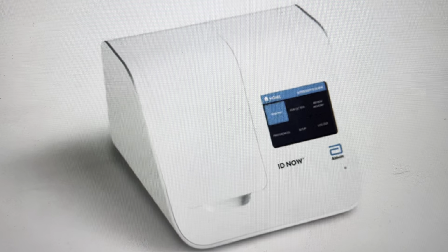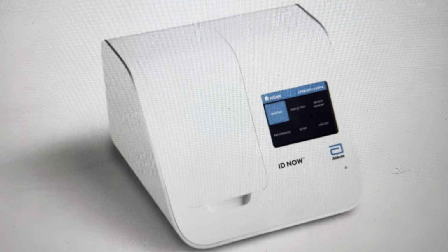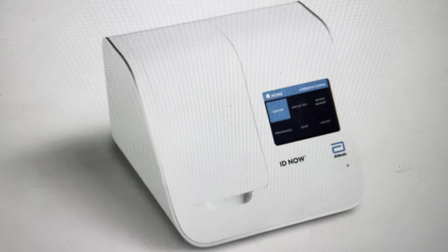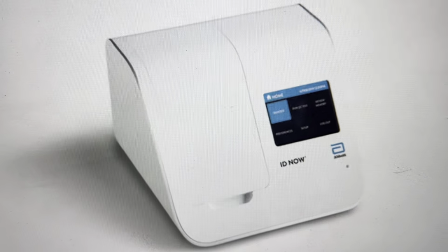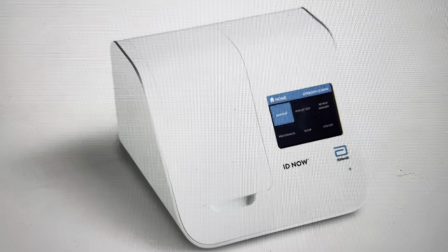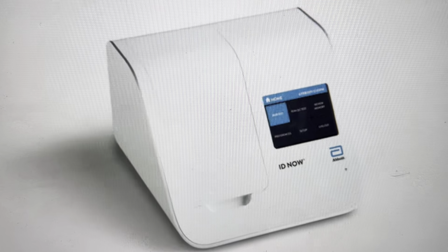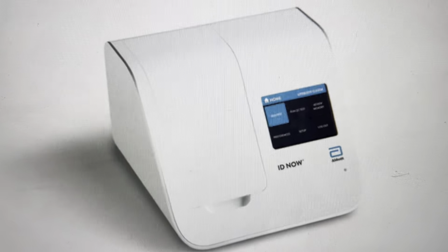Hey everybody, this is a quick video in case you have an Abbott ID Now molecular tester for the flu and other things, and you need to do a hard reset to the factory default settings on it.